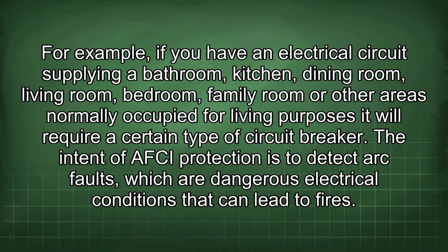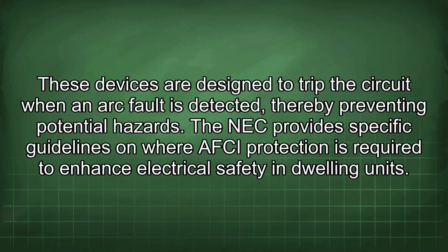For example, if you have an electrical circuit supplying a bathroom, kitchen, dining room, living room, bedroom, family room, or other areas normally occupied for living purposes, it will require a certain type of circuit breaker. The intent of AFCI protection is to detect arc faults, which are dangerous electrical conditions that can lead to fires. These devices are designed to trip the circuit when an arc fault is detected, thereby preventing potential hazards. The NEC provides specific guidelines on where AFCI protection is required to enhance electrical safety in dwelling units.